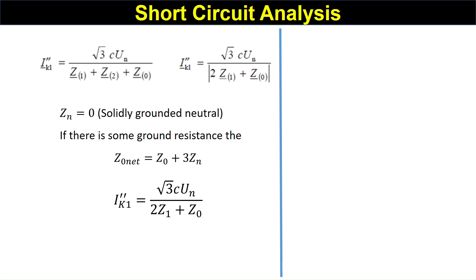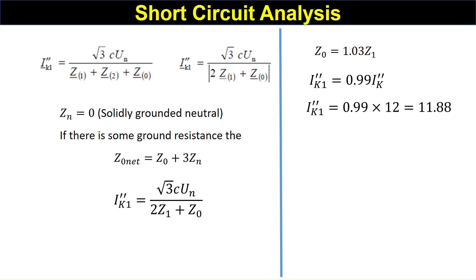So I_k1 double dash becomes root three times c_un divided by twice Z1 plus Z0. Putting Z0 equal to 1.03 times Z1, it becomes I_k1 double dash equal to 0.99 times I_k double dash (the three-phase initial symmetrical short circuit current). Putting in the value of I_k double dash, which is 12 kiloamperes in our example, I_k1 double dash becomes 0.99 times 12, which equals 11.88 kiloamperes. This is the initial symmetrical line-to-ground fault current.